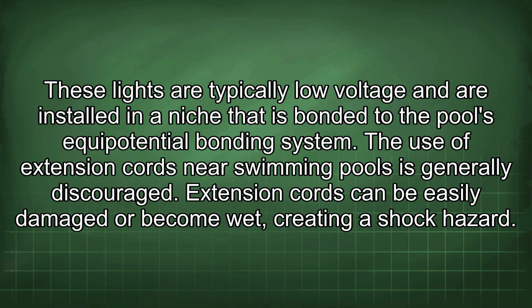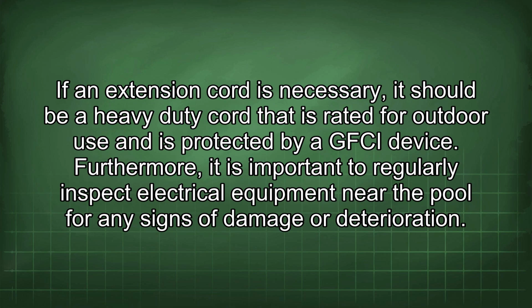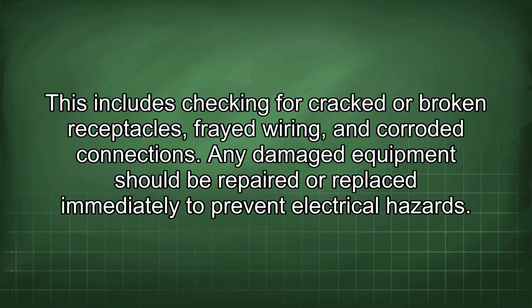The use of extension cords near swimming pools is generally discouraged. Extension cords can be easily damaged or become wet, creating a shock hazard. If an extension cord is necessary, it should be a heavy-duty cord that is rated for outdoor use and is protected by a GFCI device. Furthermore, it is important to regularly inspect electrical equipment near the pool for any signs of damage or deterioration. This includes checking for cracked or broken receptacles, frayed wiring, and corroded connections. Any damaged equipment should be repaired or replaced immediately to prevent electrical hazards.